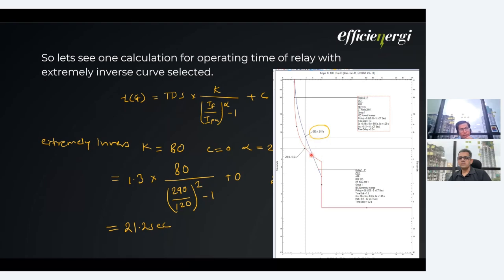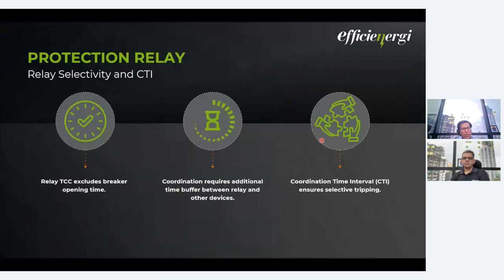Now it is the understanding of the coordination engineer to use this time with the proper tolerances, and that is where the coordination time interval comes into the picture. So here, as I said, the relay TCC excludes the breaker opening time. Coordination requires an additional time buffer, that is what we call a CTI. So the coordination time interval ensures selective tripping.